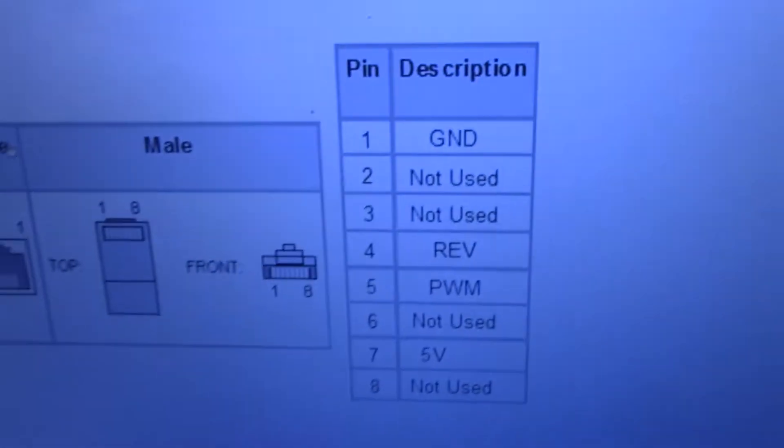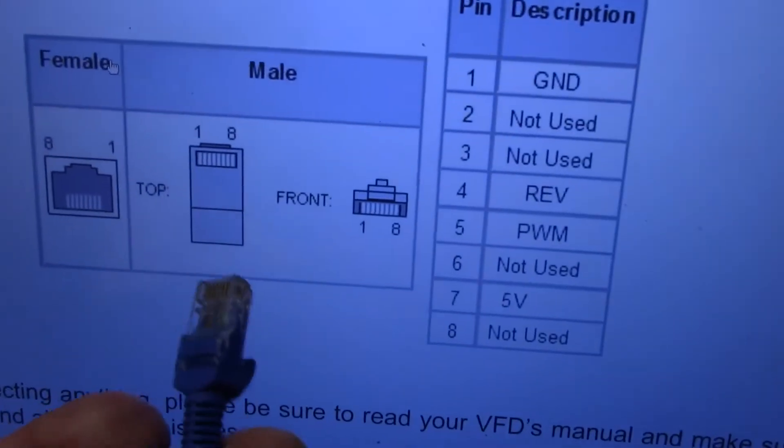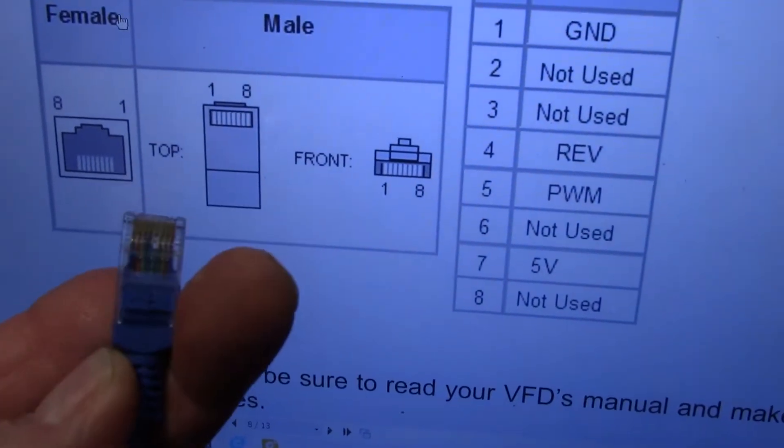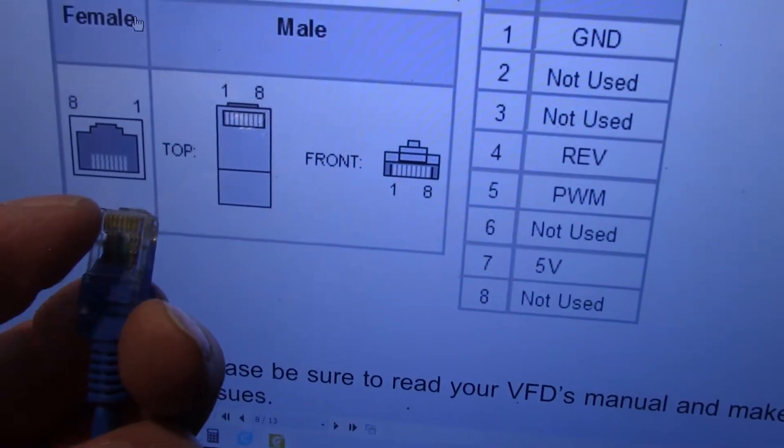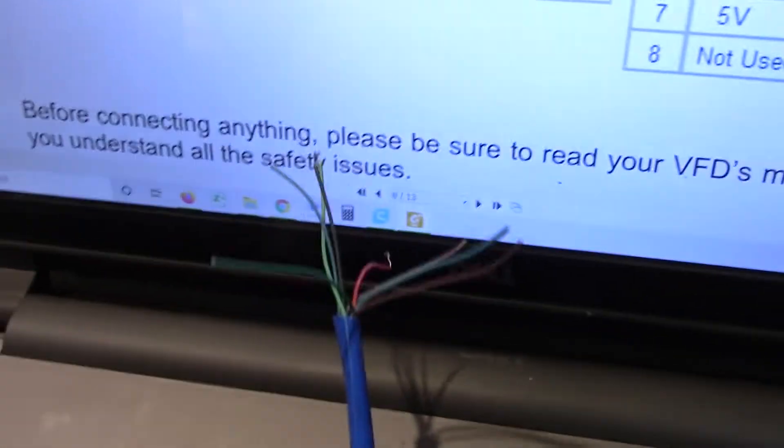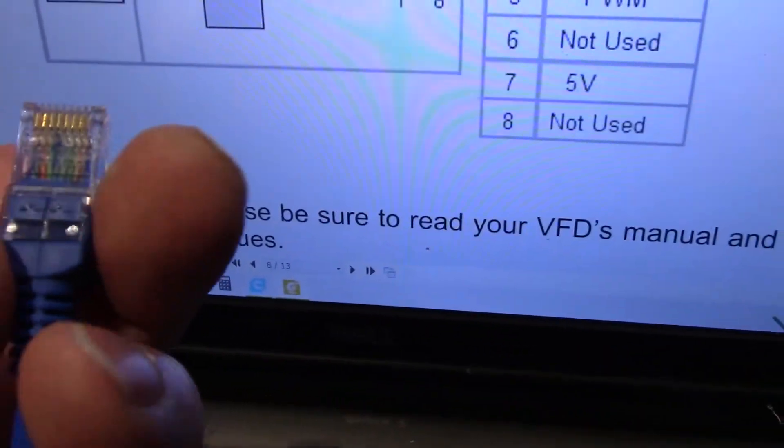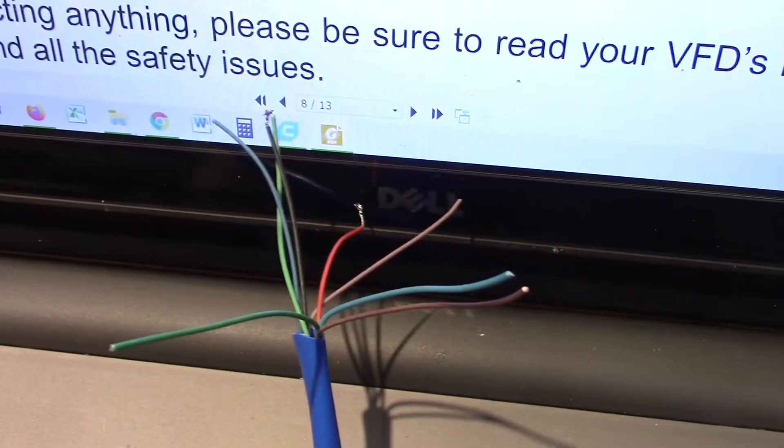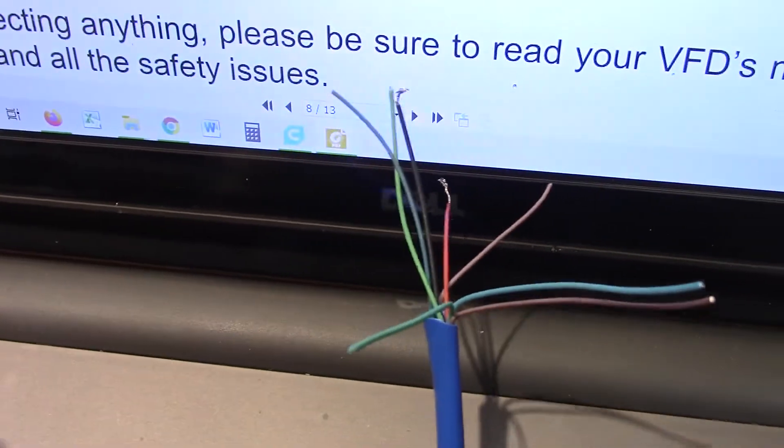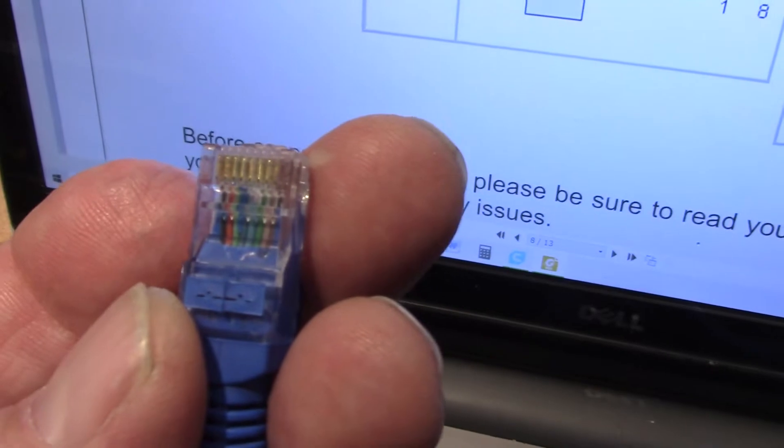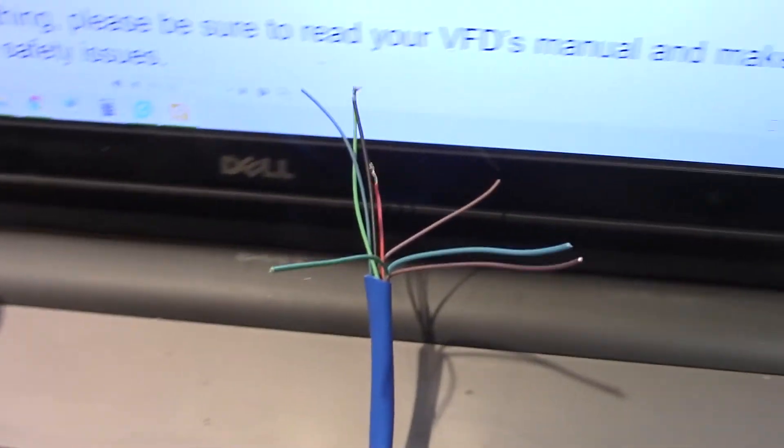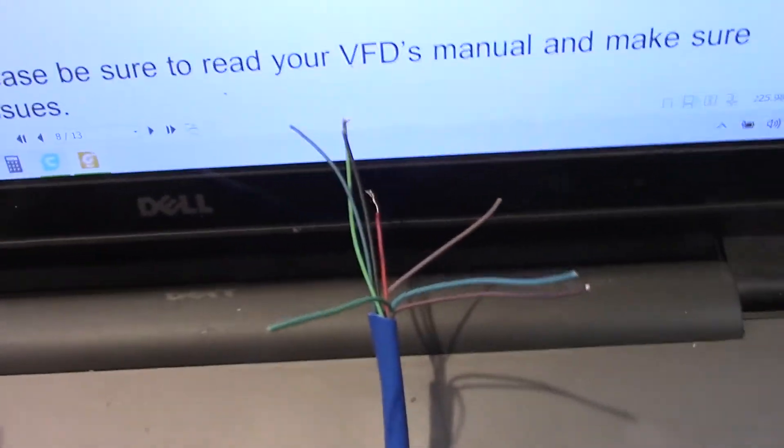So the inputs to here are this. So you can see right here, if you take a cord, and you hold it like this, see your clips on the bottom, pin one's over here and pin eight is over here, just like it says right there. So pin one, the first one, so you're going to take it, you're going to strip it out like that at the end. And so get you a voltmeter and check from this first pin, come down here and see which wire that is. And you can look in here through that clear, and you can see what color it is, and then transfer it down here and it helps you find it. But I would check it with a voltmeter and make sure you've got the right wire before you do that.